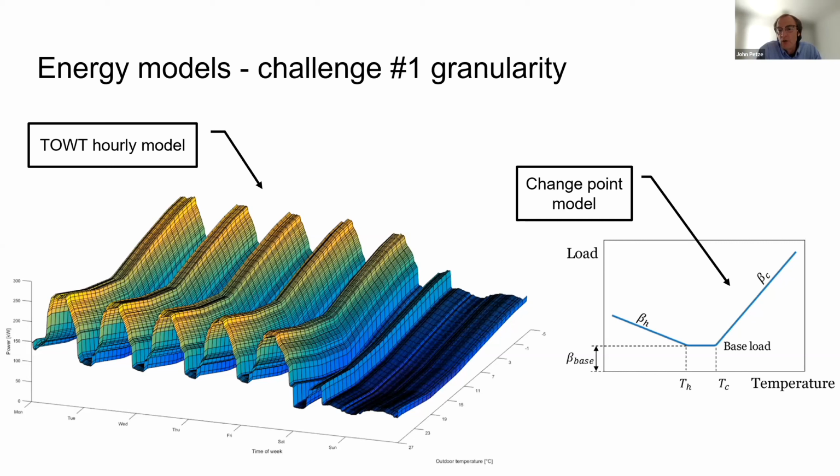I'll talk about some tools. Data quality tools would be used to detect missing data when it's expected. So you can detect that we've been getting data every 15 minutes and now we didn't. You can overwrite that data with interpolation. You can mark that you have missing data, what's considered NA data. You can also look at magnitude of change and say this is a bad reading and interpolate for that period of time. There are a variety of data quality and data markup algorithms that can be used. But again, there isn't one approach to use for all types of data.